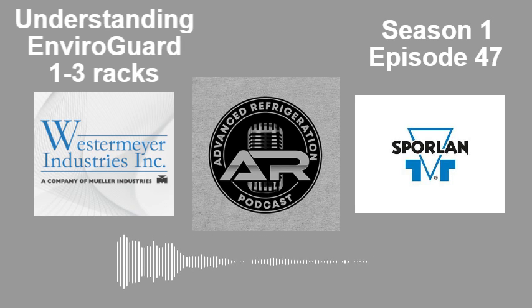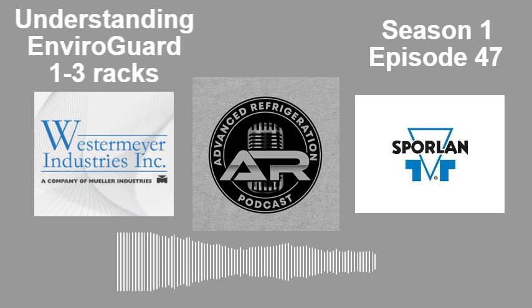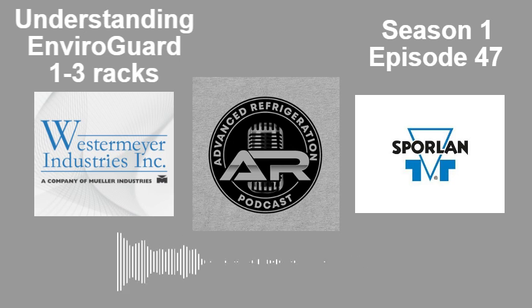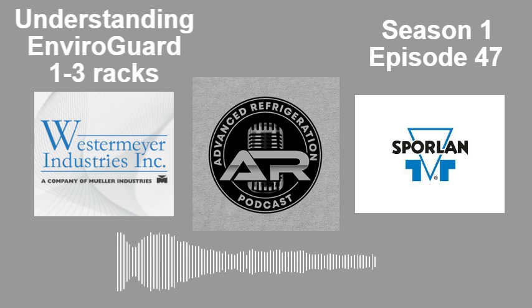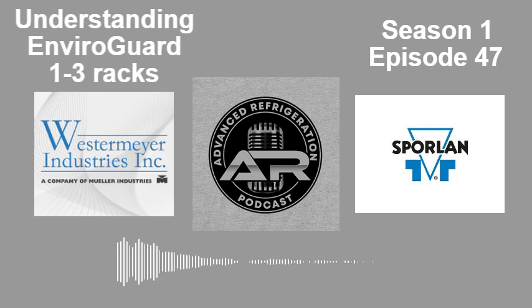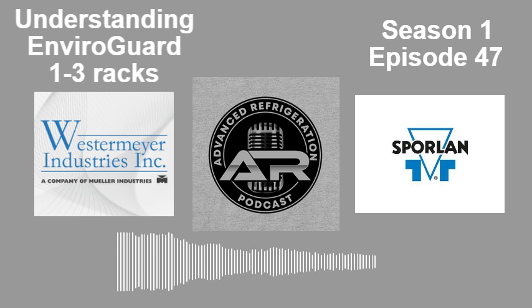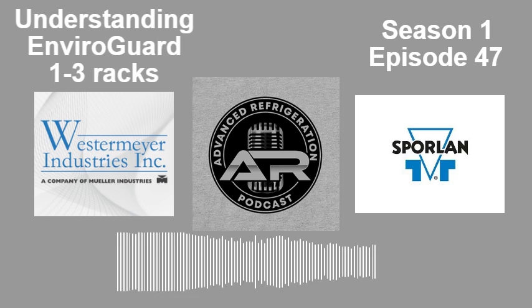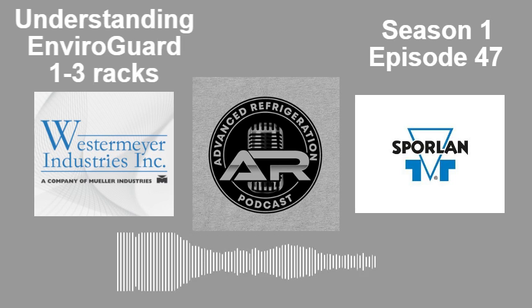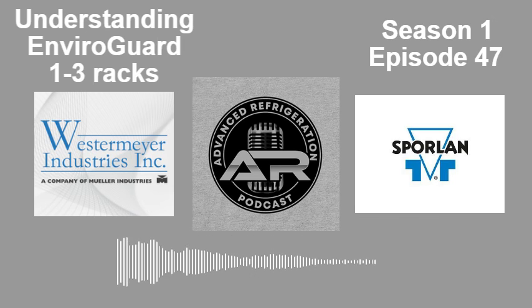I'll tell you what, the biggest thing that makes Enviro-Guard kick ass is putting a digital compressor on your lead compressor, or a VFD. It runs so much better. I mean, all these little problems guys have go away. With a digital compressor or a VFD, you're able to match the load so much better. It takes that Enviro-Guard from saving all that money in the energy in the wintertime with reduced head pressure.